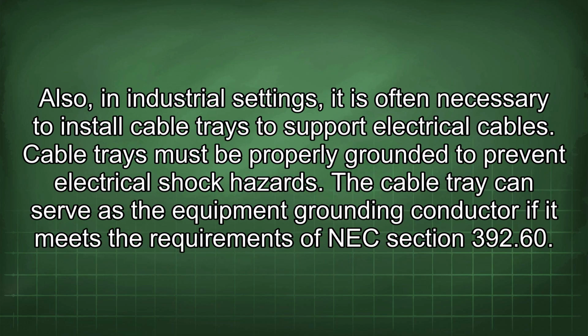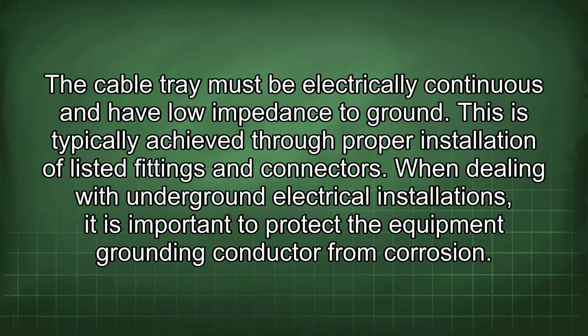Also, in industrial settings, it is often necessary to install cable trays to support electrical cables. Cable trays must be properly grounded to prevent electrical shock hazard. The cable tray can serve as the equipment grounding conductor if it meets the requirements of NEC section 392.60. The cable tray must be electrically continuous and have low impedance to ground. This is typically achieved through proper installation of listed fittings and connectors.